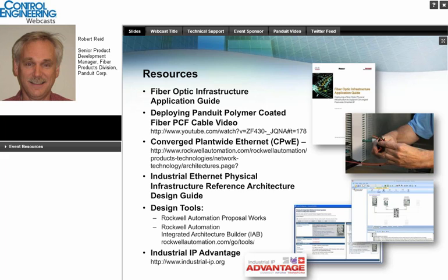Great, thanks. Is LC the only crimp-on connector type, or are there others? No, there's a long and storied history of fiber connectors that are crimp-on. There's a lot of field bus-style connectors, the versatile link connector as an example, Toslink connectors for some Japanese industrial automation controls that are crimp-on and quick terminating, plastic optical fiber, crimp-on termination, ST connectors. There are some SC solutions. So no, in terms of rapid termination, this particular connector doesn't own the market.